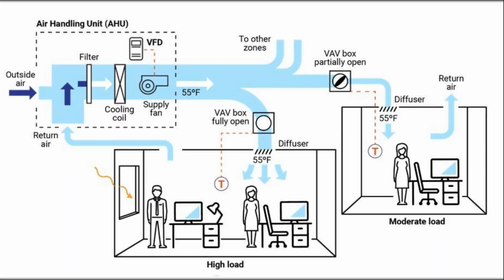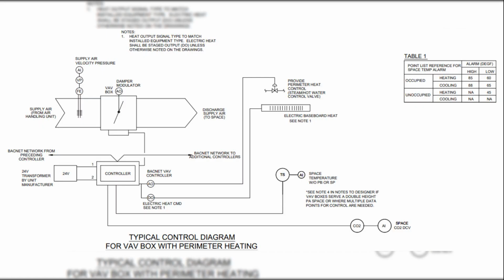A variable air volume box, or VAV box, is a small but very important part of the HVAC system in a school. Think of it as a traffic controller for the air that comes from the air handling unit. Instead of always blasting the same amount of air, the VAV box adjusts how much air is delivered to a zone, based on what's actually needed for comfort. Here's how it works. Air comes from the main air handler through the ductwork and enters the VAV box. Inside the box, there's a damper, basically a movable blade, that opens or closes to regulate airflow. If the classroom only needs a little cooling, the damper partly closes and reduces the air. If the room warms up and needs more cooling, the damper opens wider to let more air through.